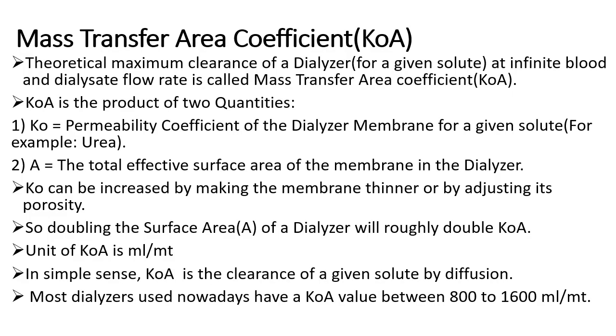The next characteristic is mass transfer area coefficient, or K0A. K0A is defined as the theoretical maximum clearance of a dialyzer for a given solute such as urea at infinite blood and dialysate flow rates. K0A is the product of K0 — the permeability coefficient of the dialyzer membrane for the given solute — and A, the total effective surface area of the membrane. K0 can be increased by making the membrane thinner or by adjusting its porosity, and doubling the surface area roughly doubles the K0A value.